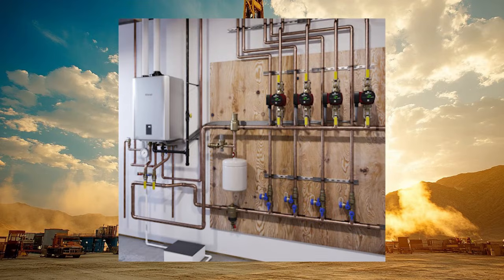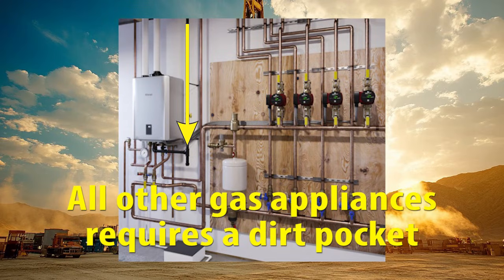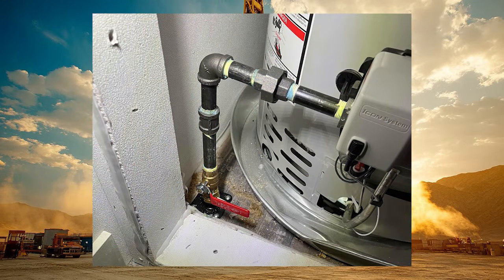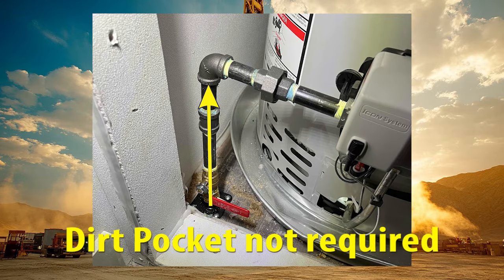So when I speak that out in human terms, that means whenever a gas line drops down to any appliance other than that long list that I gave you, it needs a dirt pocket. What we can also deduce from this is if we have a gas line traveling up to an appliance above us and there's no dips in the pipe, we do not need a dirt pocket.